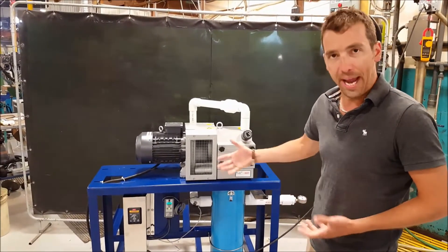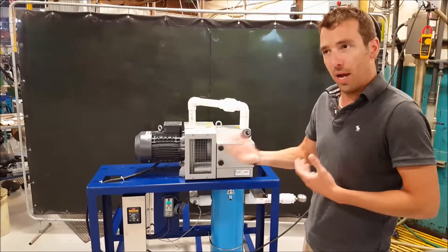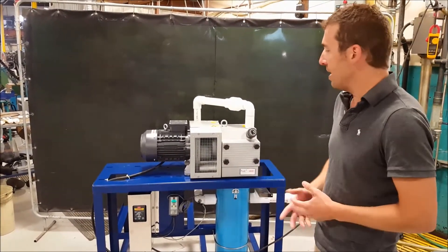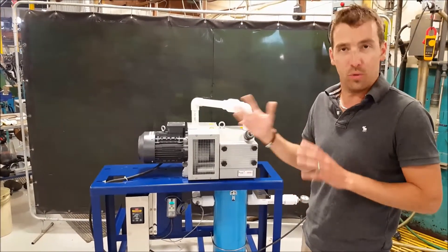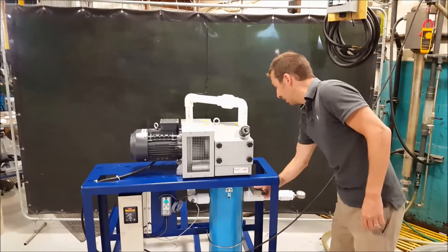I'm just going to create a leak, so the pump will speed up to give us more CFM capacity. And as soon as it reaches the demand, that 20 inches of mercury, it will slow down again. Let's take a look.